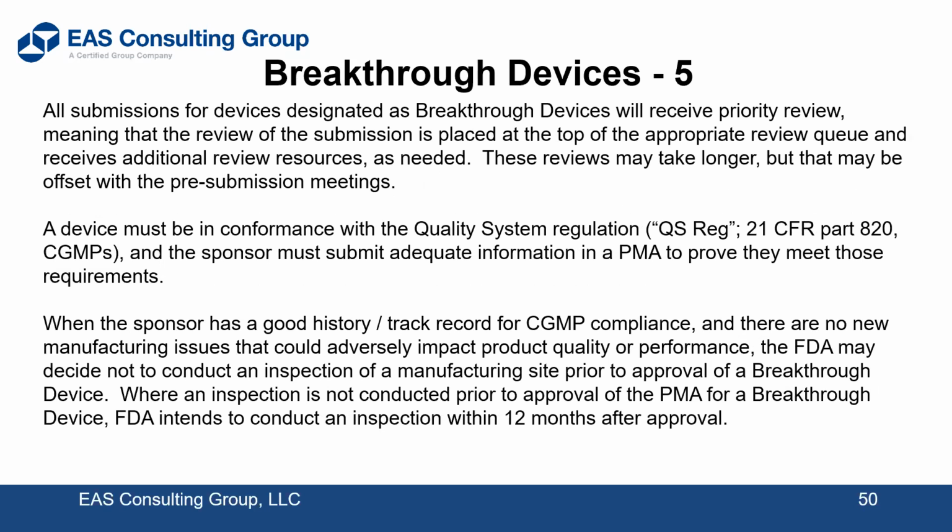But the second bullet point, or key point that I see neglected many times with smaller companies or startup companies, the device must be in conformance with the QS reg, that's 21 CFR 820, or the CGMPs for devices. Now it says you have to submit it in a PMA. They might even do a pre-inspection of you, but not with a 510K. The assumption is you are in compliance. And as I said before, many times the consultants are called in because after the fact, they weren't in compliance. They didn't have a design history file. That's one of the biggest failings right there, or a risk management file under 14971.